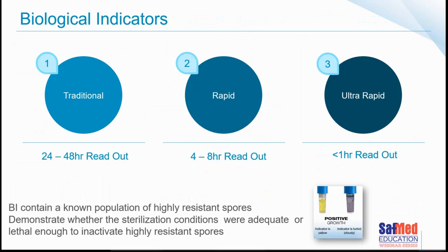Moving on to chat about biological indicators. In the early days, biological indicators were simply spore strips. There weren't any vials. It was a spore strip that was placed inside the steam sterilizer. After the sterilization process, the spore strip was then put into a vial and incubated. Of course, the self-contained biological indicators that we know today were introduced in the 1970s, and there are three main types.